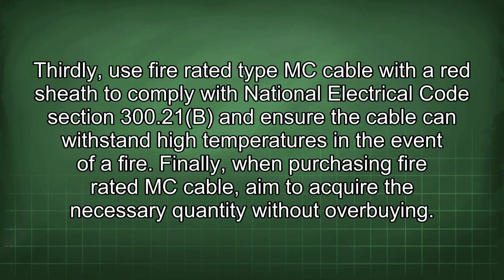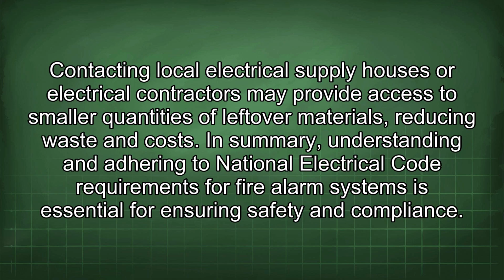Thirdly, use fire-rated type MC cable with a red sheath to comply with National Electrical Code Section 300.21b and ensure the cable can withstand high temperatures in the event of a fire. Finally, when purchasing fire-rated MC cable, aim to acquire the necessary quantity without overbuying. Contacting local electrical supply houses or electrical contractors may provide access to smaller quantities of leftover materials, reducing waste and costs.